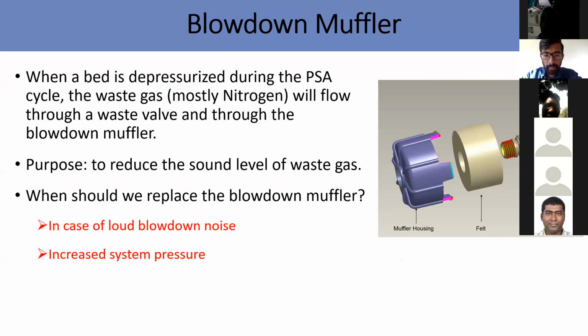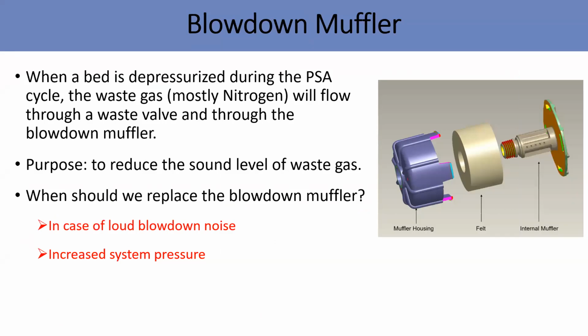So on the alarm system, they got low pressure oxygen. Then oxygen concentrator, I think I did mention earlier. So that's one of it. Blowdown muffler. These are normally near the compressor unit. So what happens is to control the noise and clear the waste in the proper way. So these are mostly to flow the nitrogen through this particular thing.